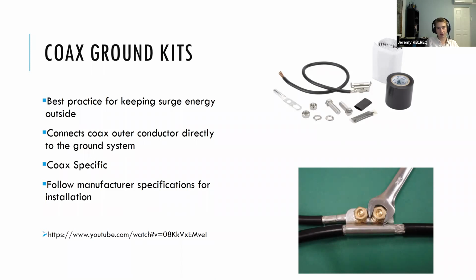Again, it keeps most of that surge energy outside. Normally it's flowing in that cable, and that cable's going inside eventually. With these ground kits, you get a nice low impedance to ground, and it's going to keep most of that current flowing outside.